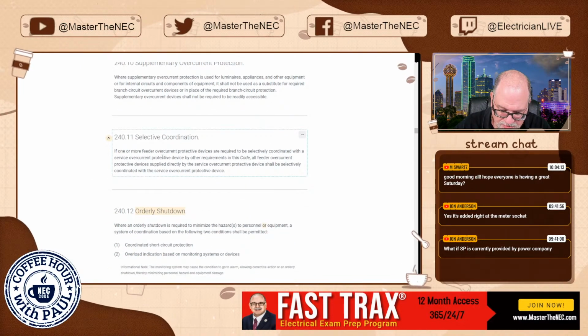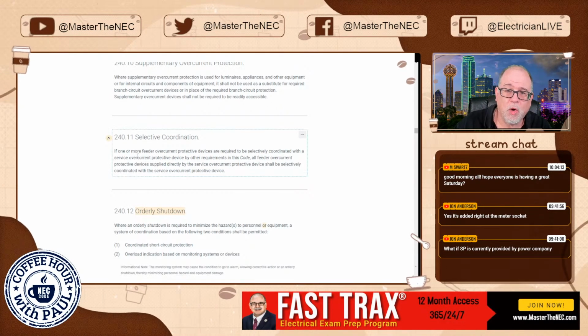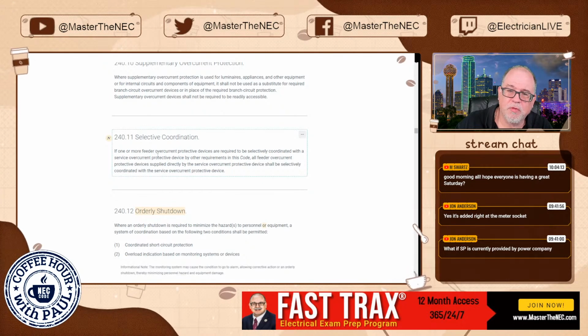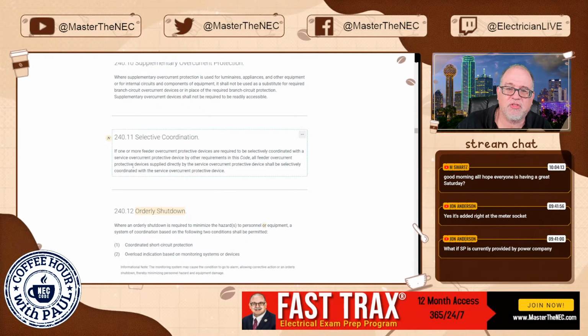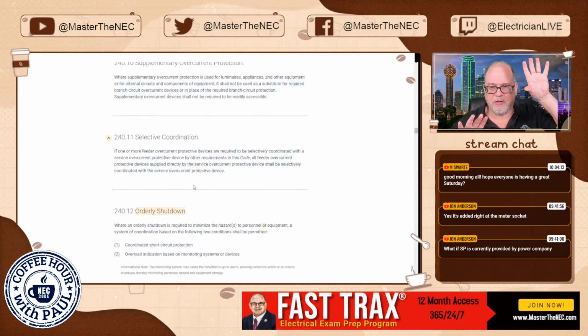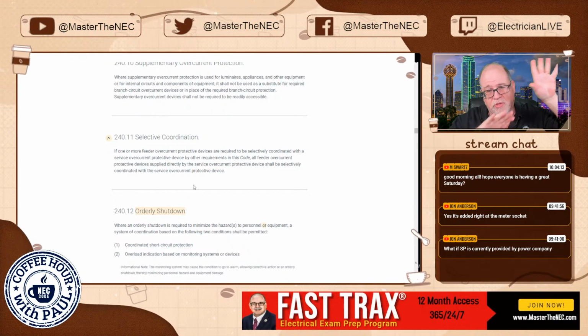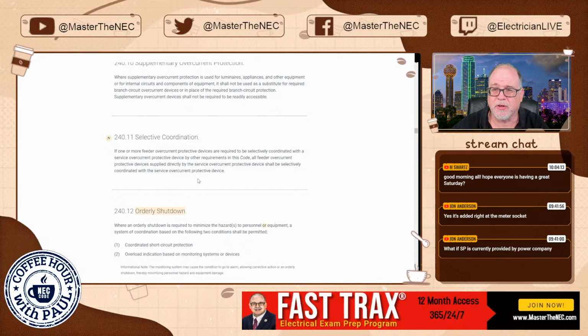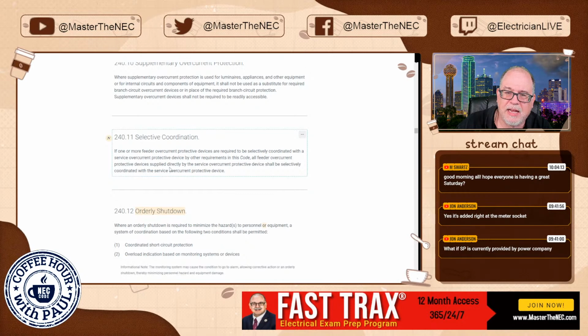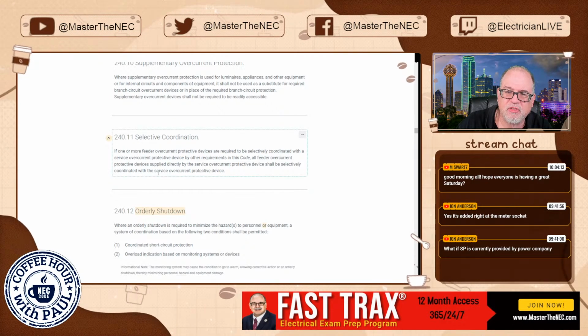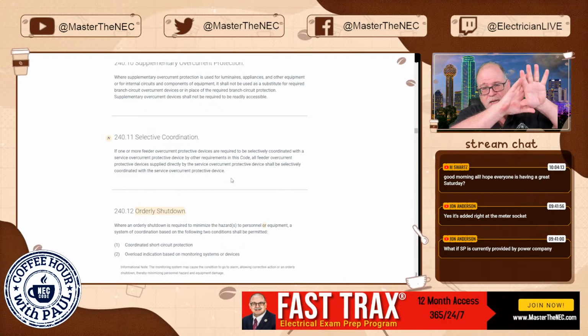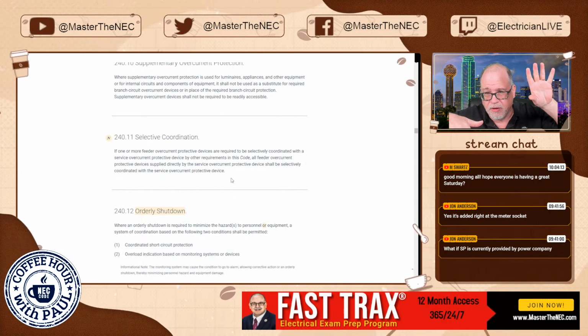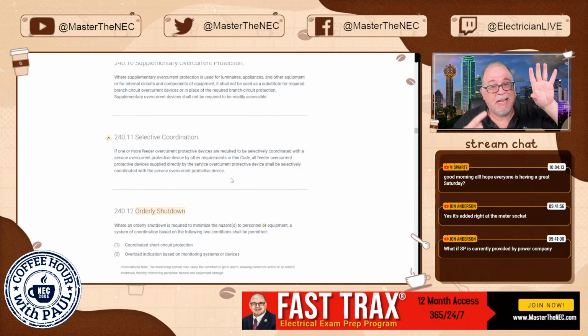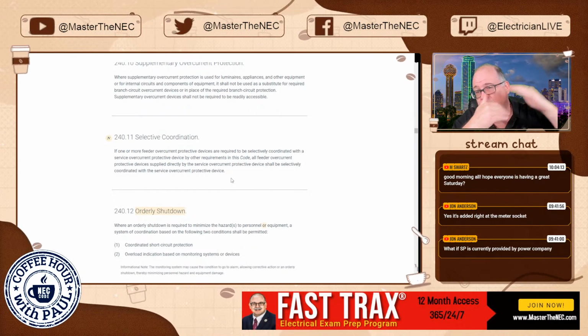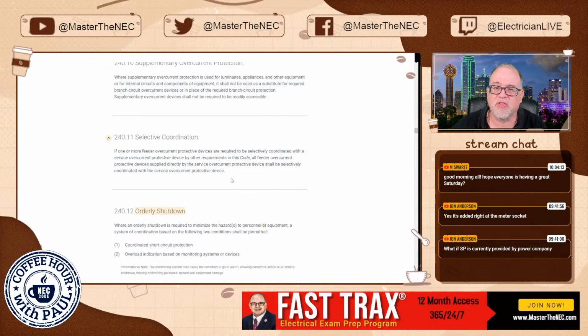Selective coordination 240.11. Let's see here. If one or more feeders, overcurrent protective devices are required to be selectively coordinated with a service overcurrent protective device. So, you got service and you got feeder downstream. If they're required to be selectively coordinated somewhere else in the code, like healthcare facilities or emergency systems or whatever, it says all feeder overcurrent protective devices supplied directly by the service overcurrent protective devices shall be selectively coordinated with the service overcurrent protective devices. So I could have a service disconnect, and then out of that, on the load side of that service disconnect, I have a feeder, right? And it is basically supplied directly from the service overcurrent protective device. If they're required to be selectively coordinated, then it has to coordinate with that service overcurrent protective device.